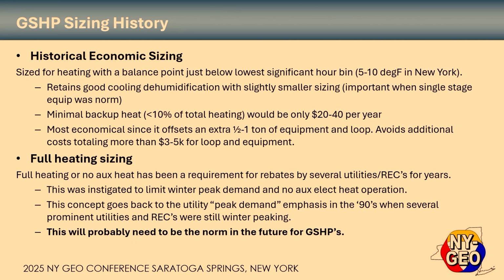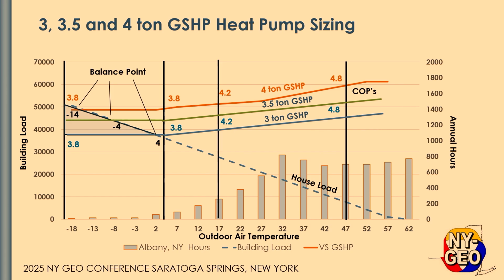This will probably be the norm for all future ground source heat pumps, is to really do that full sizing, because that peak demand issue, as we talk about the healthiness of the grid, that is an important thing. So let's take a look at a ground source heat pump, and I've got multiple sizes on here so you can kind of see the effect of that.